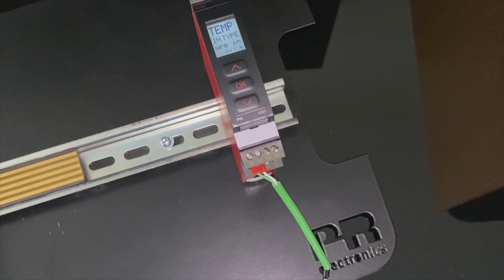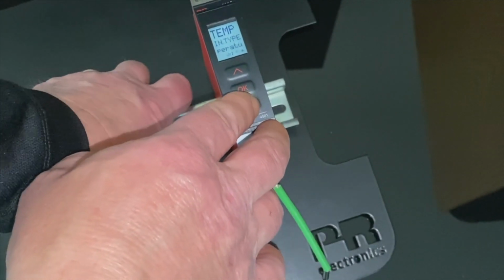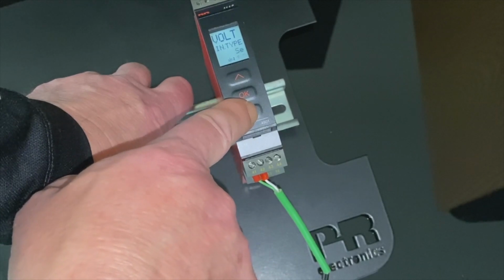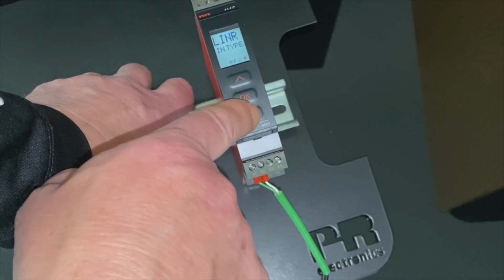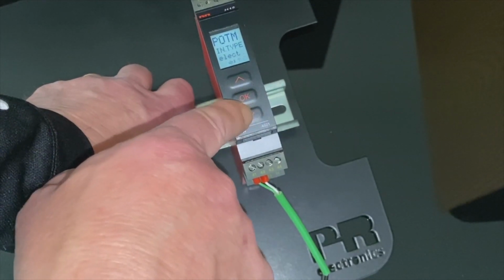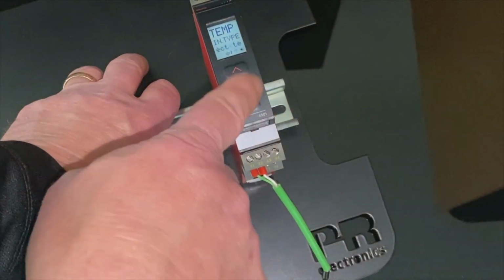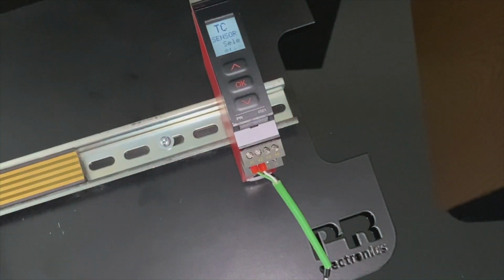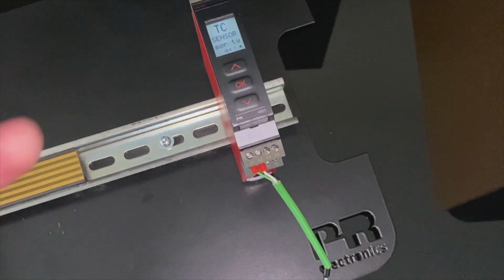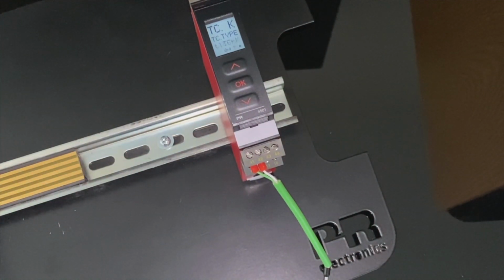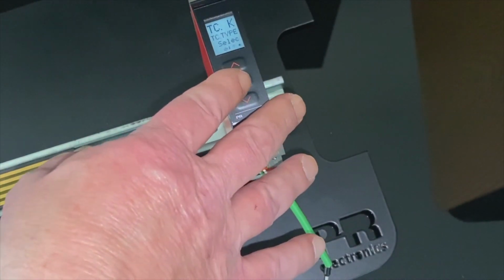It's important to know you won't find this on the menu selections, but the 4116 can power any 2-wire transmitter, and it also takes multiple inputs, as we discussed. So if you scroll through here, you'll see that we do temperature, voltage, current, linear resistance, potentiometric signals. All those types of inputs we can process. So you select temperature. And this happens to be a thermocouple, as you know, that we're working with, and it's a type K. So now it's asking you, are you measuring temperature with a thermocouple or an RTD? Know that you can do 2, 3, or 4-wire RTDs with no problem, and that there are 13 different types of thermocouples. Right now it's defaulted to K because I've been working with this device, but you simply scroll through the menu and you'll find your perfect thermocouple.